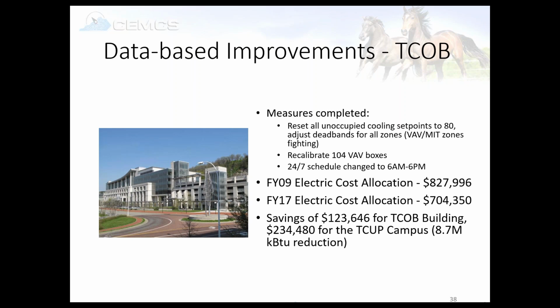But these systems kind of fought each other. It's an open floor space. So one thing we did, kind of a no-brainer, was adjust and make consistent all the cooling and heating set points through the building, so we could at least agree on that. We recalibrated 104 VAV boxes, or worked with maintenance to do that, and revised the schedule from 24/7 to 6 to 6. These are pretty easy things to do.